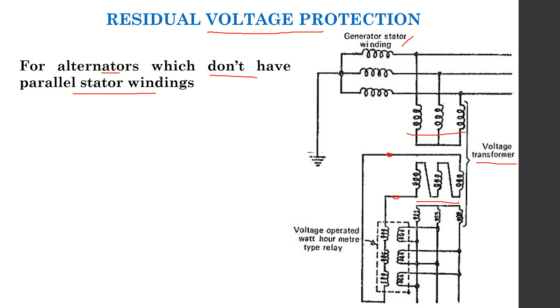This is your primary of the voltage transformer, and this is your secondary of the voltage transformer. The secondary of the voltage transformer is connected in broken delta form. That is, here the relay is connected and the relay is fed with the residual voltage. The residual voltage is the sum of the voltages of the secondary of the voltage transformer.